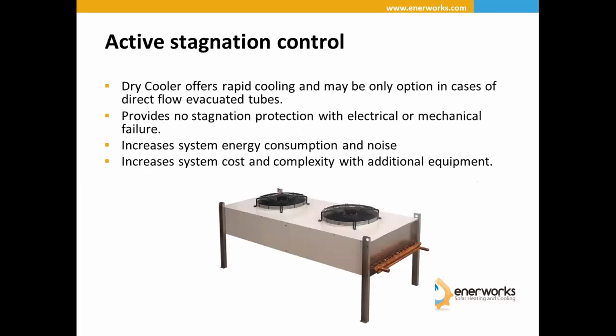So a lot of people's first choice to control temperature is what I'll call active stagnation control. And this is something that you're actually familiar with for air conditioning systems, chillers, which is a type of cooling system. So a dry cooler would be something to maintain temperature below a certain level. But the one challenge, and I've used these in projects, is if your dry cooler fails, or if the pump in the system fails, or you lose electricity, you don't have any active control at that point because it's no longer working.